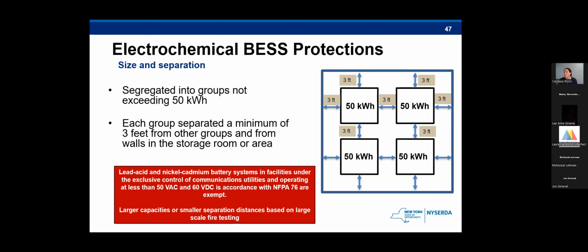There are two exceptions to this requirement. One is for communication utilities, and the other one is based on large-scale fire testing. As we spoke about earlier, there is one requirement that, based on large-scale fire testing, there will not be propagation of fire or any other hazards. This requirement can be changed per the fire code official, and often for walk-in units, smaller separation distances are allowed based on the results of that large-scale fire testing. So I think this is probably the most frequent exemption that you'll see in the code, regarding size and separation.